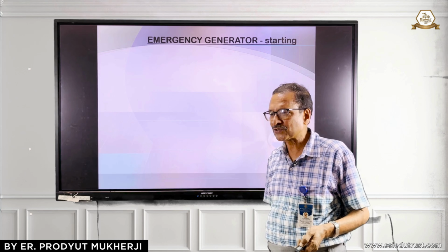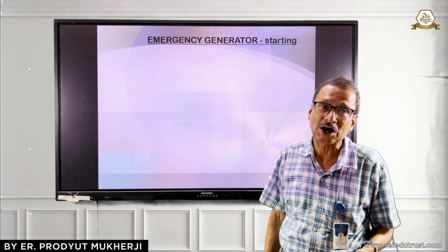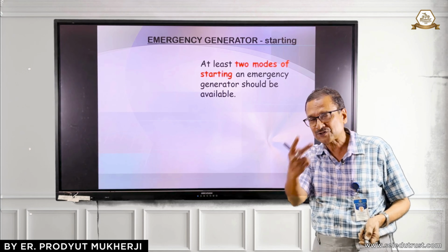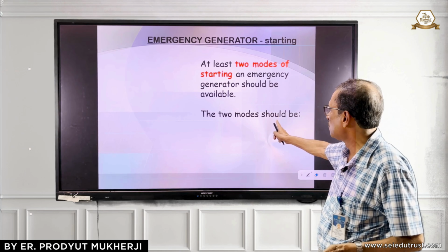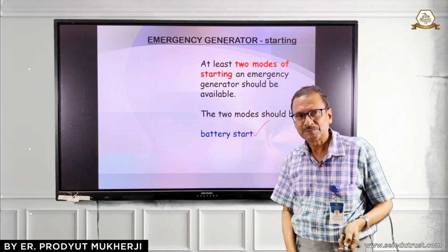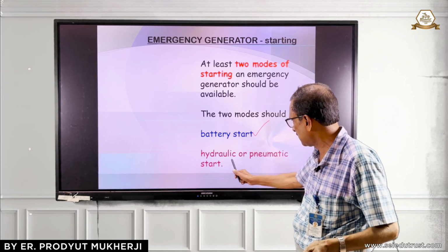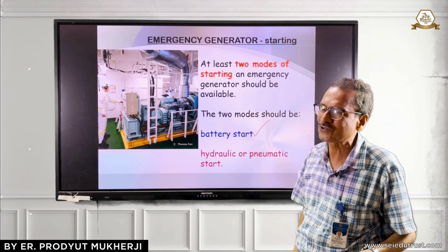Now let us see the starting of an emergency generator. What's the regulation for starting of an emergency generator? At least two modes of starting must be there. The two modes: battery start, that is compulsory. It must have a battery start. And another option, either it can be a hydraulic or it can be a pneumatic start.